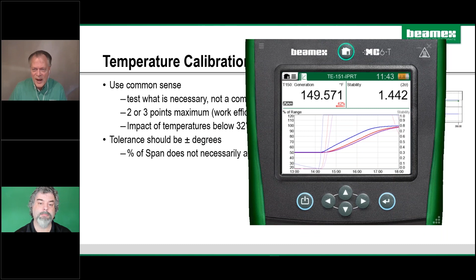So doing multiple points just for checking out its accuracy is a waste of time. I mean, you could even consider doing 2 points because the line is the line. Now, if you're wanting to check a profile of something, there are instances where you might want to do 10% steps, because you're wanting to look at a correction factor across a critical zone of temperature.